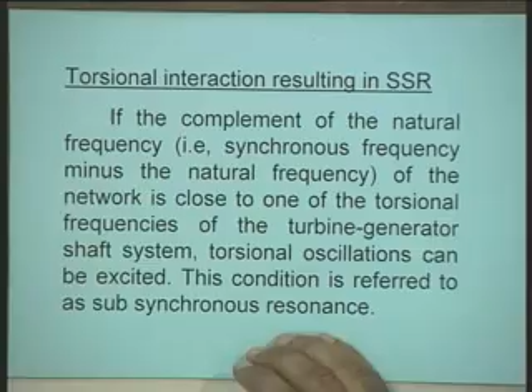Another aspect which I have to emphasize here is the torsional interaction resulting in SSR. As I told you, so far as the induction generator effect is concerned, there is no interaction with the torsional modes, and this is basically a circuit phenomenon. When we talk about torsional interaction resulting in SSR, if the complement of the natural frequency, that is the synchronous frequency minus the natural frequency of the network, is close to one of the torsional frequencies of the turbine generator shaft system, torsional oscillations can be excited.